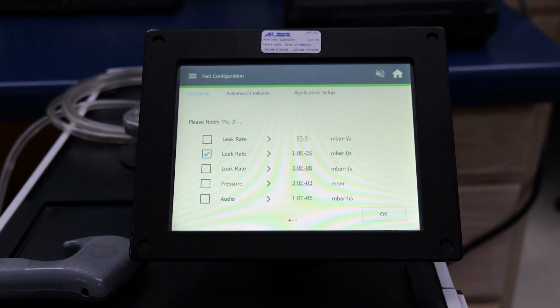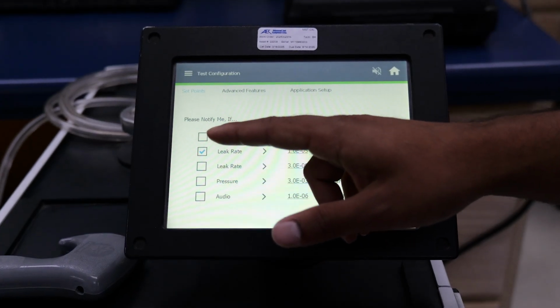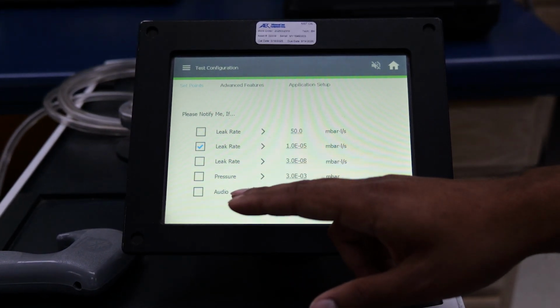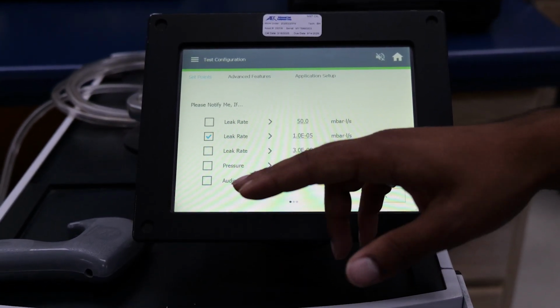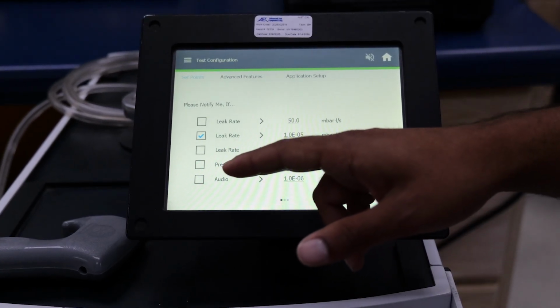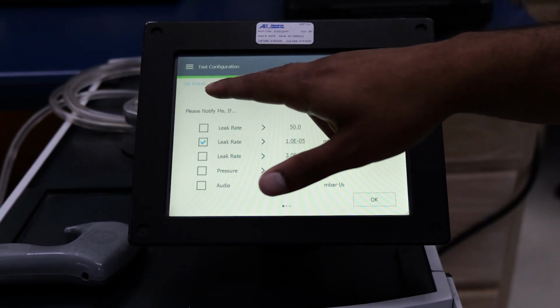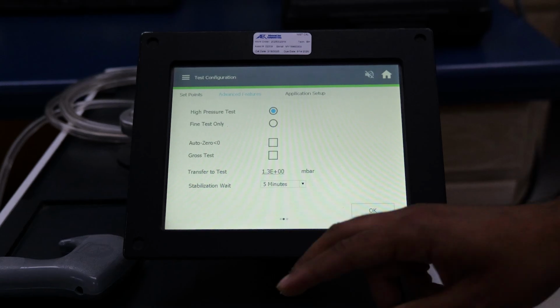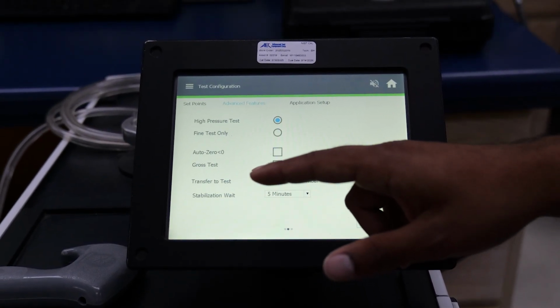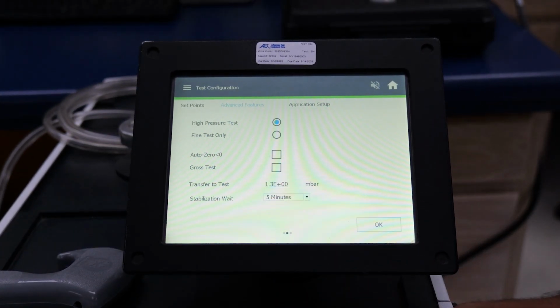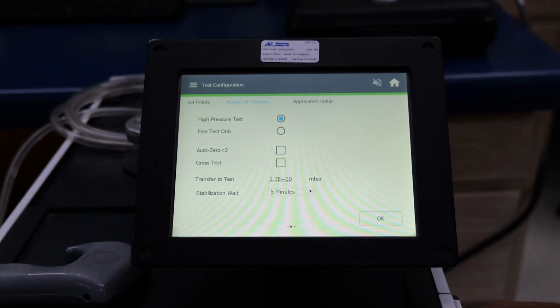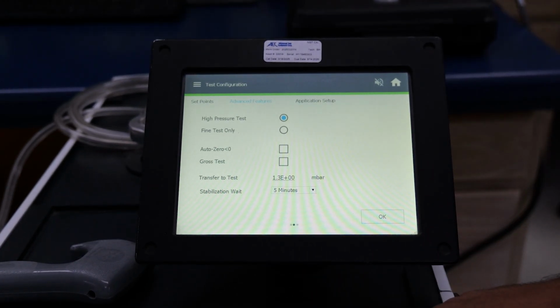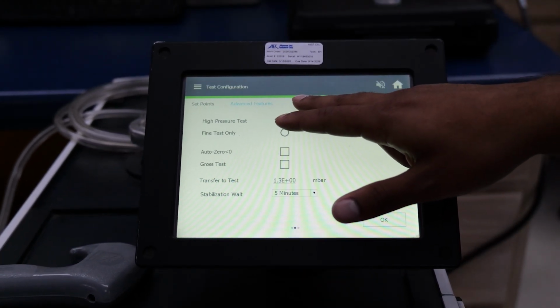We can come over here to test configuration, and you can set different test points that you would want to be notified if it reaches a certain leak rate or pressure. We can go over here to advanced features and see different types of features as well with the different test points, auto zero, gross test, and how long you'd want stabilization wait to show up for.